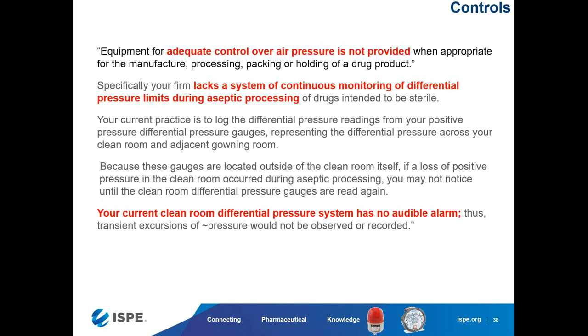The other thing is pressure differential. Isn't that important to us? If we lose the pressure differential in a facility, what happens? Outside air rushes in. Shouldn't we always know the temperature, the humidity, the pressure differential, and the particulate count? These are all interrelated, especially particulate counts, and there have been 483s regarding the design.